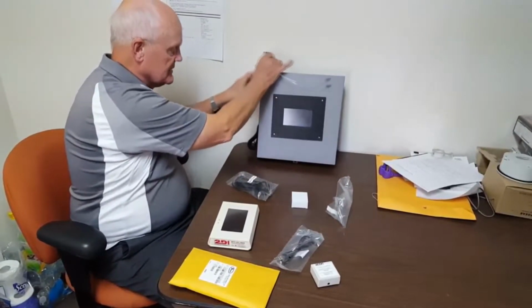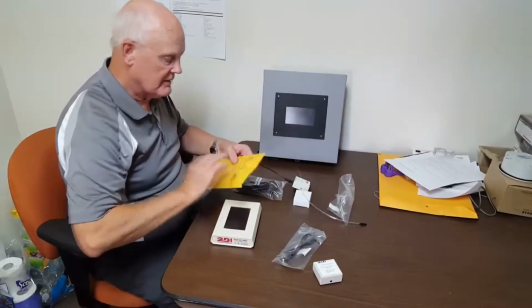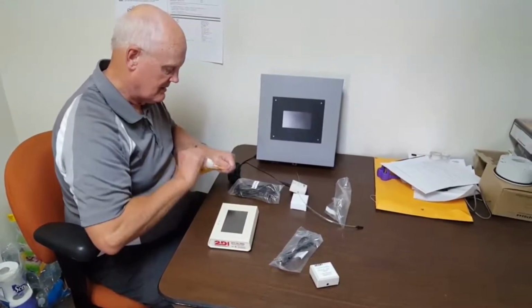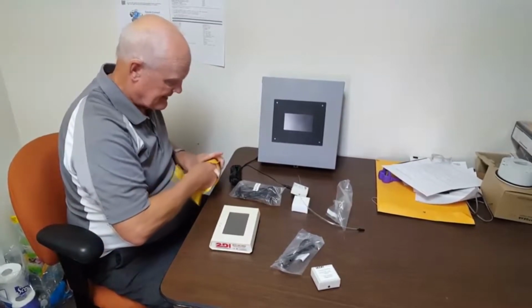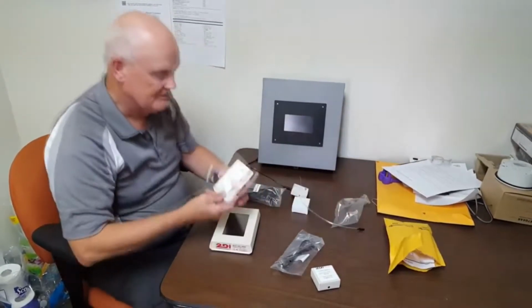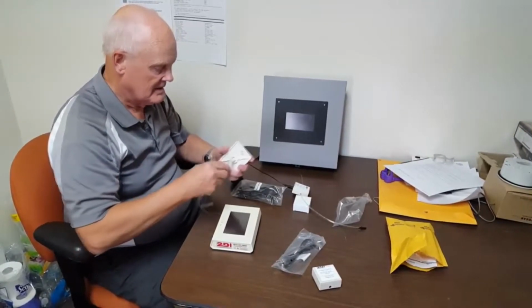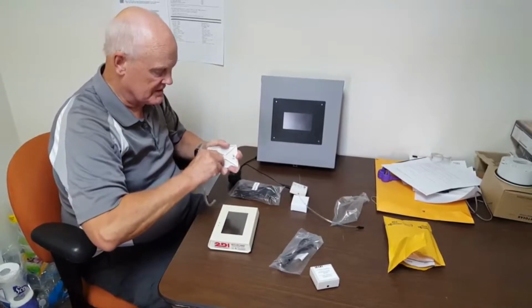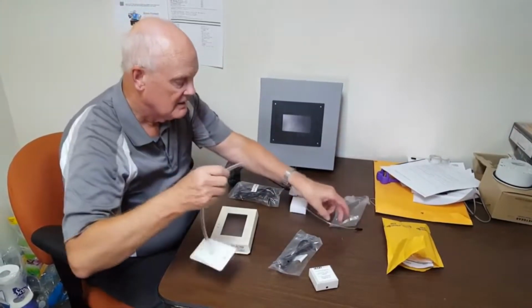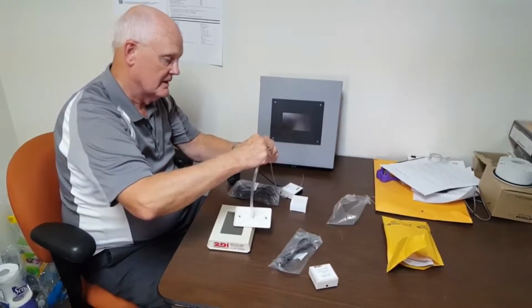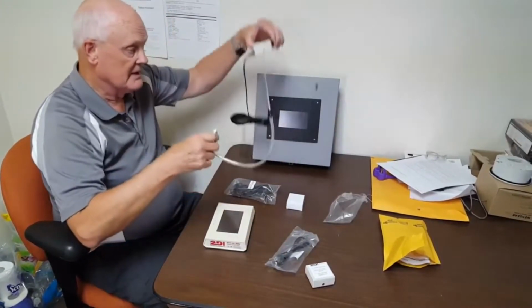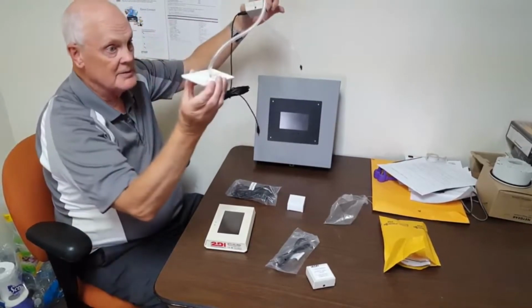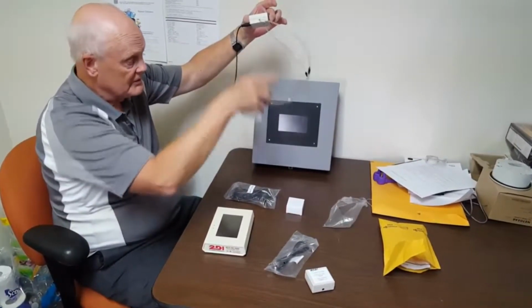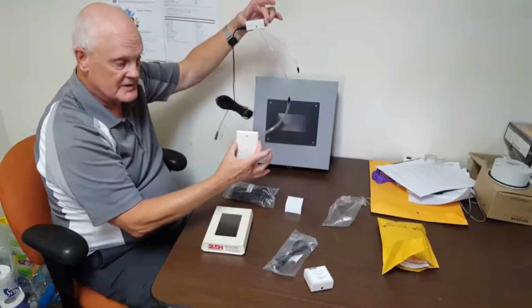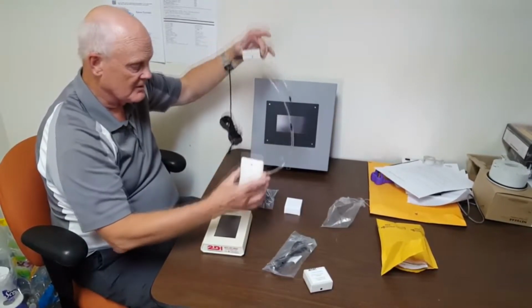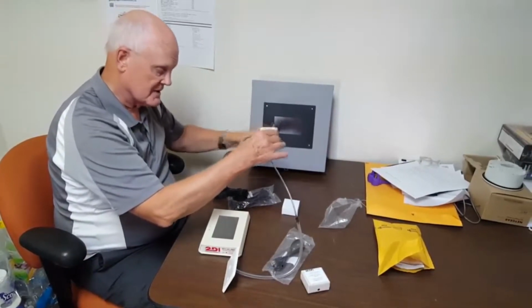To make a nice clean installation, we have a passive port which looks like this. One end of this tube goes on here, and the other end goes in here. So if this is mounted up in the ceiling or on the joist, it can be put in the ceiling or wall if you want to run it down inside the wall, to sense the pressure on one side of the wall, and the same for the other side.